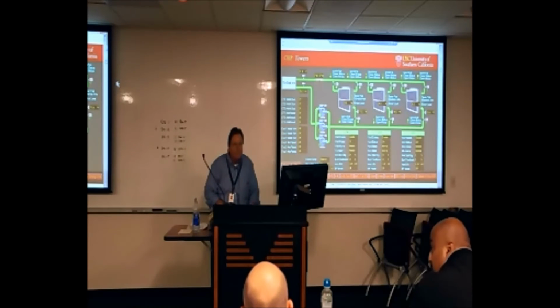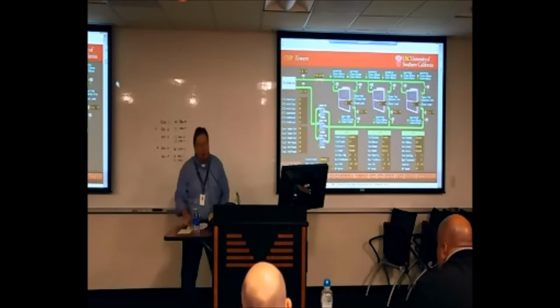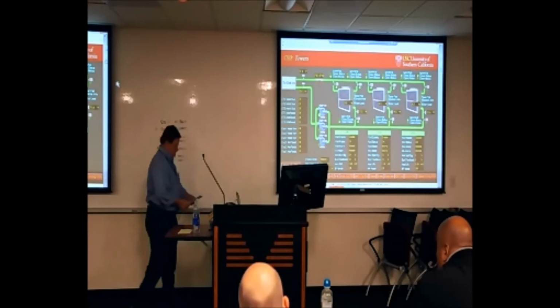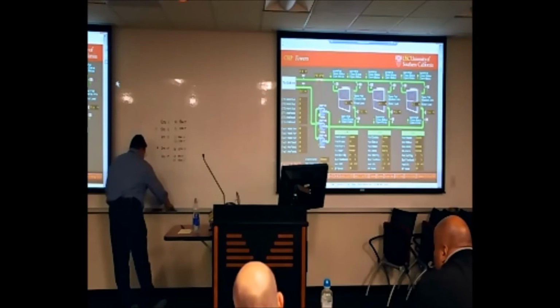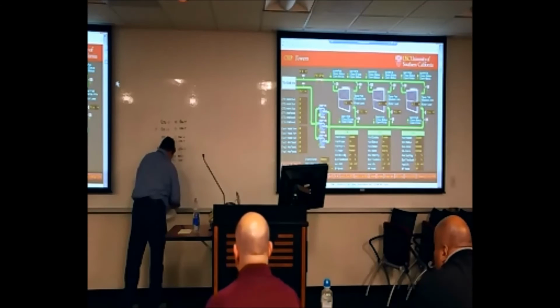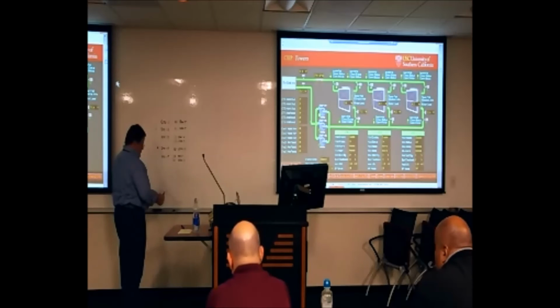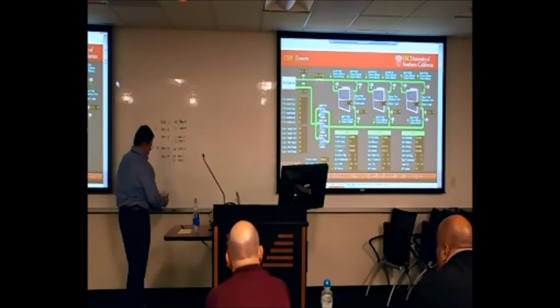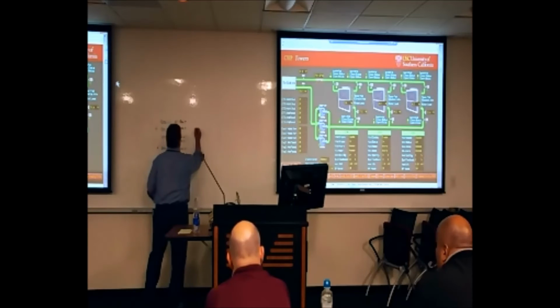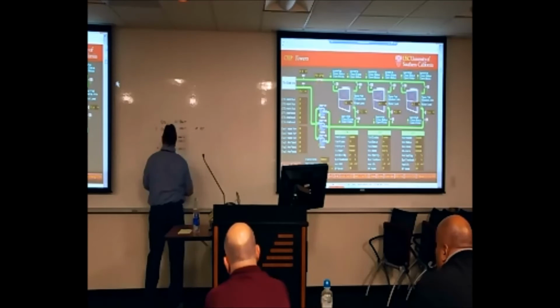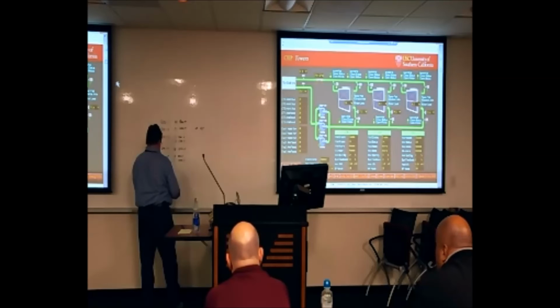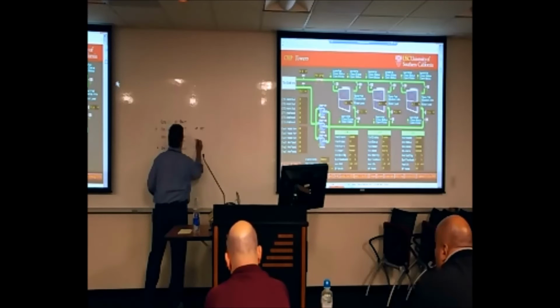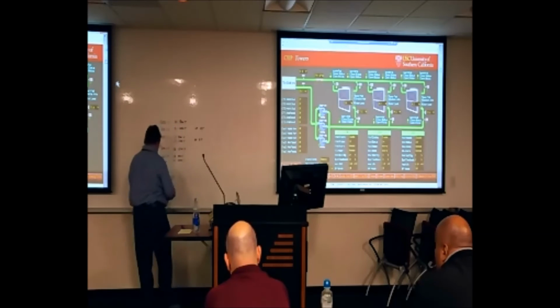Can you go to the tower staging one more time, over here? Yes. On stage 3, you've got the 800 and the 1500. What was happening with the 2 pumps and 2 towers? Yeah, I'm sorry, I should have written all that down. Stage 2 is actually 1 pump, 2 towers. Right, one pump, 2 towers. Stage 3 is 2 pumps, 2 towers.